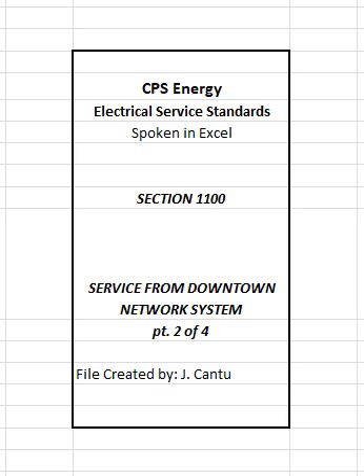F. Drainage. Customer shall provide a sump hole with 1/2 inch thick metal galvanized cover with drainage holes where water or other liquids would need to be pumped from transformer vault or room. 1. The sump hole shall have minimum dimensions of 12 x 12 x 24 inches deep or 12 inches in diameter and 24 inches deep. 24-inch depth includes 12-inch floor thickness and 12-inch sump hole.